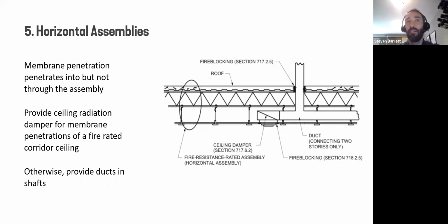And so by contrast, a through penetration, like I said, runs fully through, but a membrane penetration doesn't go all the way through. It penetrates into, so think of into the membrane, but not fully through. You can see in this graphic here that there is a duct that penetrates into the roof ceiling assembly. On the very left of this graphic, there's a big circle that says fire resistance rated assembly. It's a horizontal assembly. So this is the case where I talked about that sandwich. This is roof ceiling because the roof and the ceiling itself are all part of that assembly.